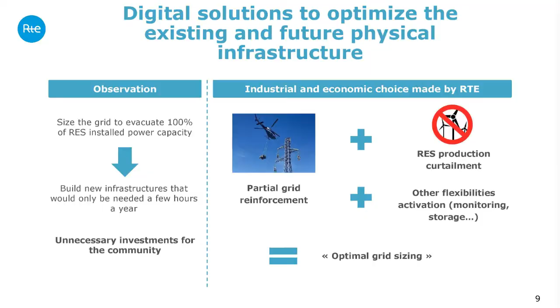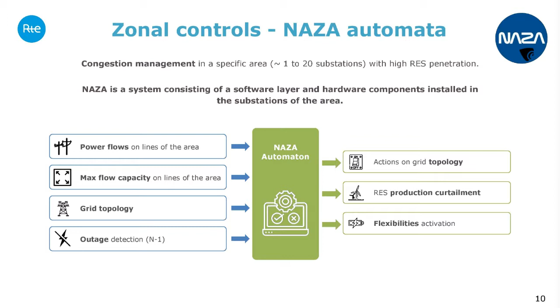What we plan to develop and deploy in the years to come is what we call automata. NAZA, in French, stands for New Adaptive Automata for zonal issues. We will have one automata for 1 to 20 substations. These automata will take into account the power flows in input, the max flow capacity on the lines, the grid topology, the outage detection, and will take automatic decisions to act on grid topology, curtail renewable production, or activate other flexibilities.